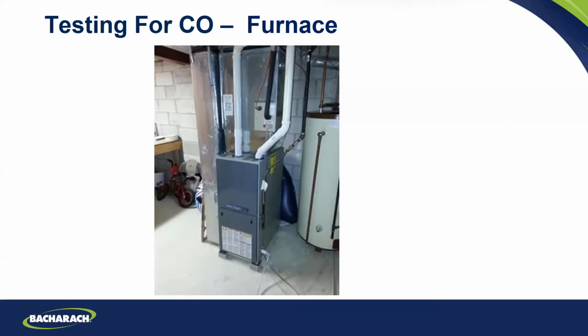You could have dirty burners. I used to have an old atmospheric furnace, and every year I would check it. It would be 55 to 60 ppm CO. I would take those burners out, clean them up, vacuum, put them back in, and it would drop below 5 every year, so that scaling would come down only on the burners. So you want to check your draft, set your gas pressure, and check for dirty burners and flame impingement. Anytime a flame touches a cold metal surface, it always makes carbon monoxide. So you want to check any places where you may have something like that.